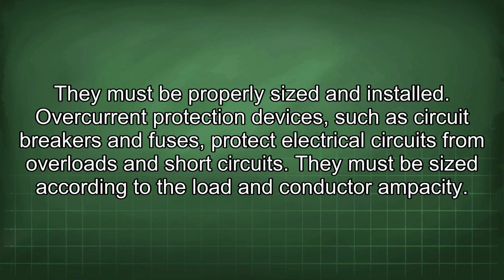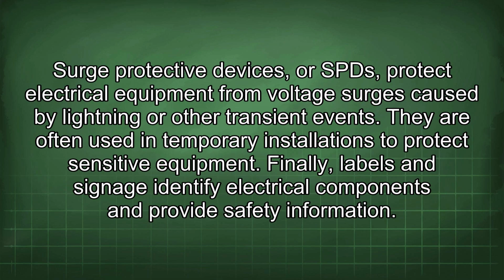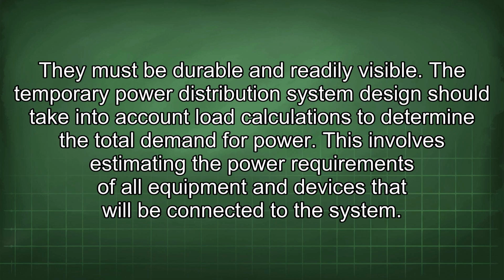Overcurrent protection devices, such as circuit breakers and fuses, protect electrical circuits from overloads and short circuits. They must be sized according to the load and conductor ampacity. Surge protective devices, or SPDs, protect electrical equipment from voltage surges caused by lightning or other transient events. They are often used in temporary installations to protect sensitive equipment. Finally, labels and signage identify electrical components and provide safety information. They must be durable and readily visible.